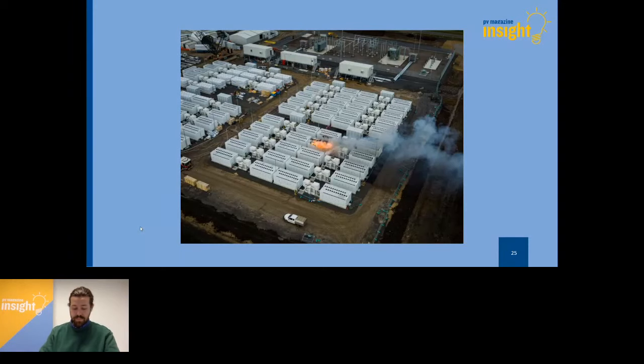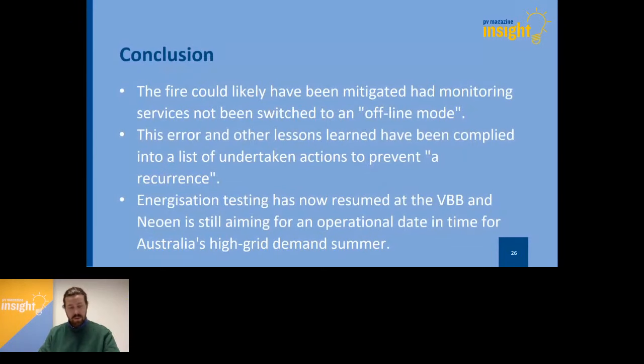In conclusion of the ESV report, the fire could most likely have been avoided had SCADA and the relevant monitoring devices not been accidentally switched to offline mode after that first megapack's duties in the commissioning process had ceased for the day. That has been addressed in the lessons learned.